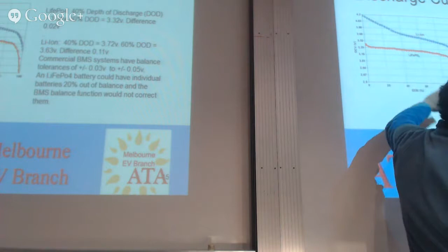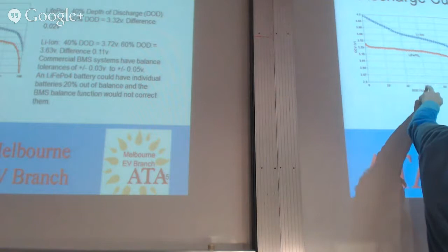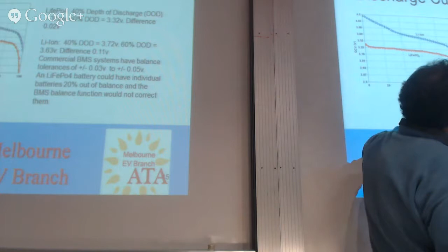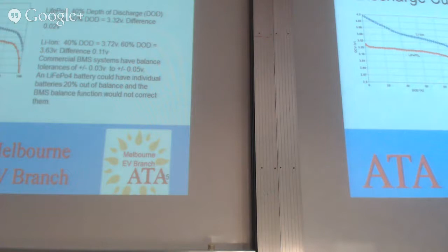And why I've mentioned that is the BMS is trying to keep that battery within balance. But between 40% discharge and 60% discharge on the LiFePO4 battery, the 0.02 volt difference will not be picked up by the BMS. Commercial BMSs aren't able to pick up such a very small difference in voltage. So the BMS will not be able to keep all the cells completely balanced within the LiFePO4 battery, whereas in the lithium-ion battery, because of the extra difference in voltage, the BMS will be able to easily keep the battery balanced. So a LiFePO4 battery could have individual cells in the pack 20% out of balance, and the BMS function wouldn't correct it.